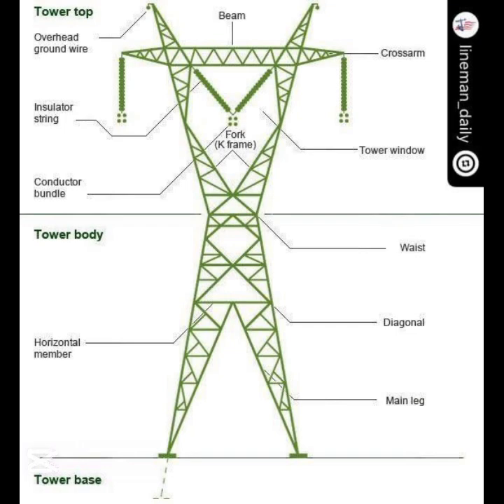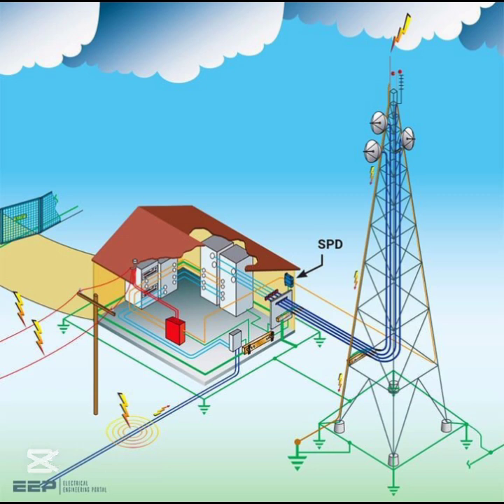Number 8. Proper tower design and placement. The design and placement of transmission towers play a significant role in lightning protection. Towers with low footing resistance, the resistance between the tower and the earth, can effectively dissipate lightning currents into the ground. Using tall structures can also help control strike points, directing lightning strikes away from critical equipment.